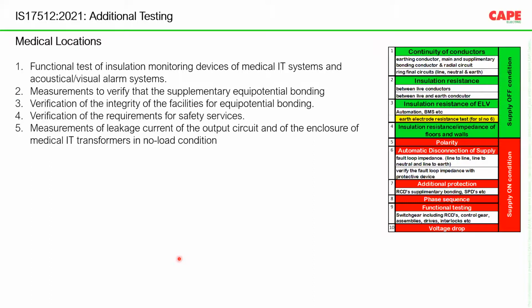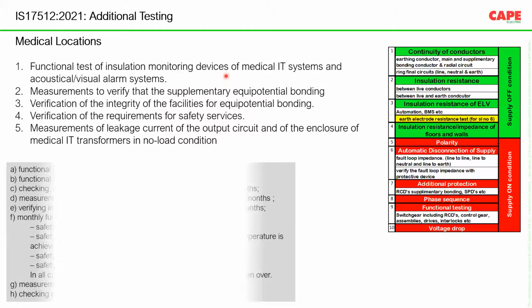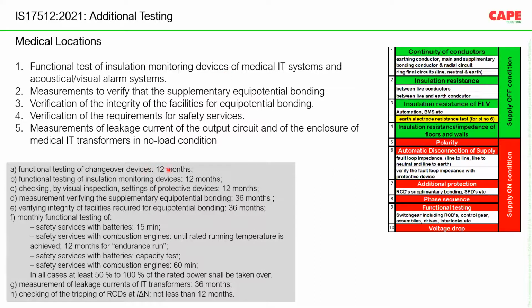Now, in addition, the last point, the medical location requires additional testing. The previous one is for the entire area, but medical location requires additional testing, because if you go for an IT supply, you have insulation monitoring devices. So insulation monitoring devices shall be tested, and it shall be tested according to the second part, the frequency of testing. For example, functional testing of insulation monitoring device every 12 months you are supposed to do.